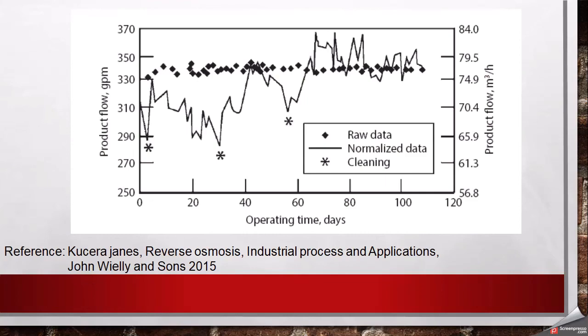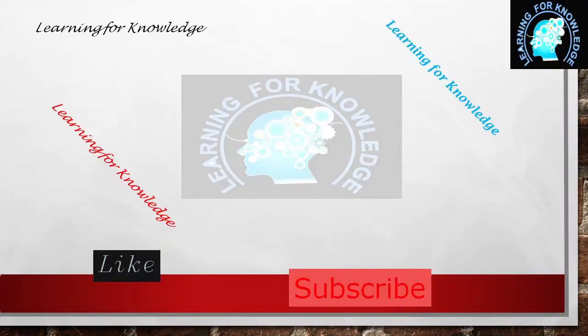I hope you enjoyed this and can understand the importance of normalization of data in a reverse osmosis system, and that by using normalization of data you can evaluate the performance of the reverse osmosis membrane. And one important thing: different manufacturers of reverse osmosis systems normally provide software for the normalization of data, so you can easily use that, or you can make your own Excel sheet for recording the data, and then you can normalize the data.